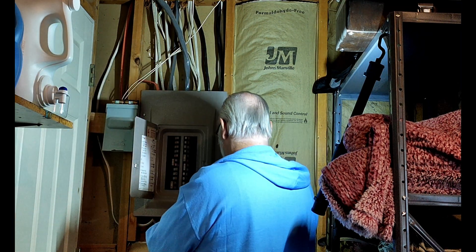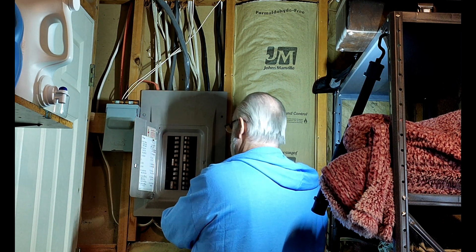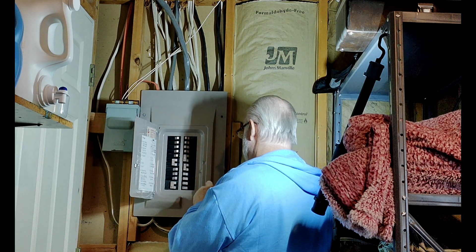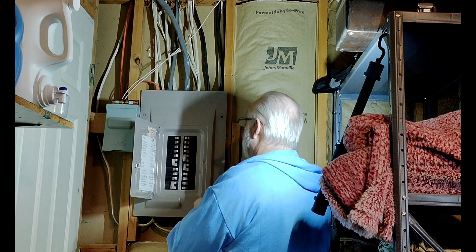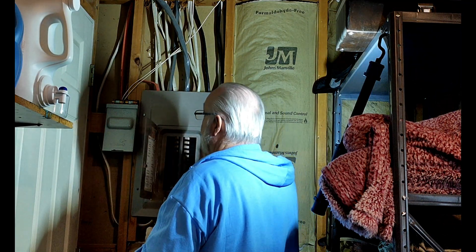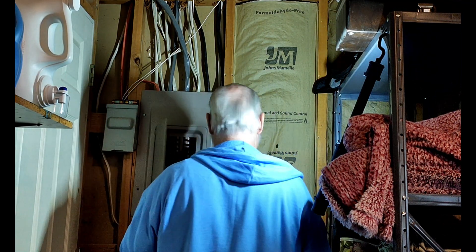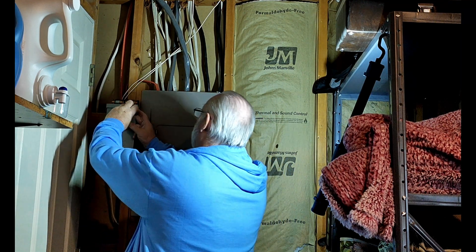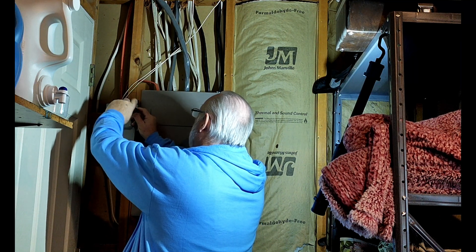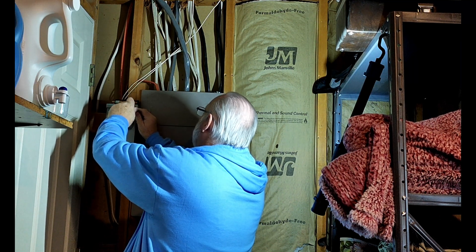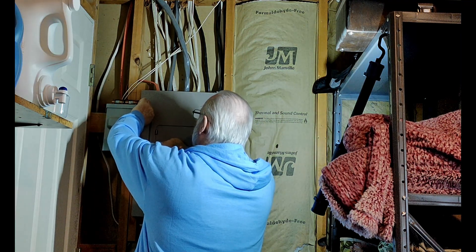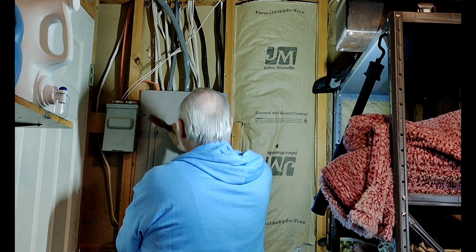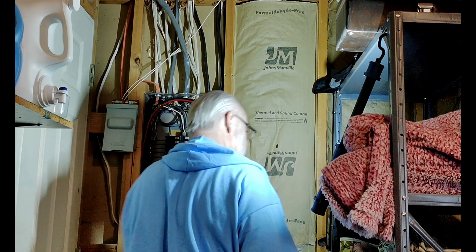Right now the box is live, so we have to be very careful what we're doing here. I want to show you while we've got power. I've pulled the quick disconnect from the AC unit because after I saw it, I was in shock. I couldn't believe that someone had done that. It's definitely a very, very large hazard.